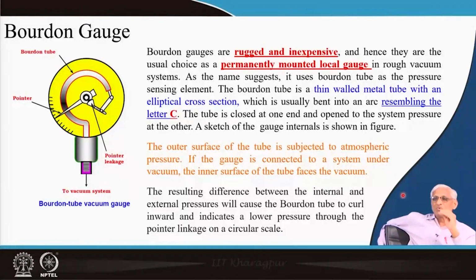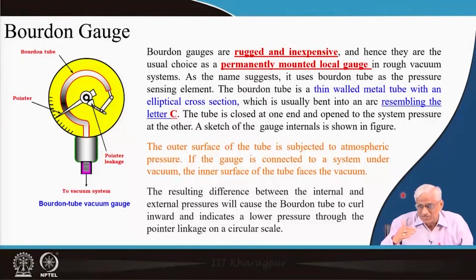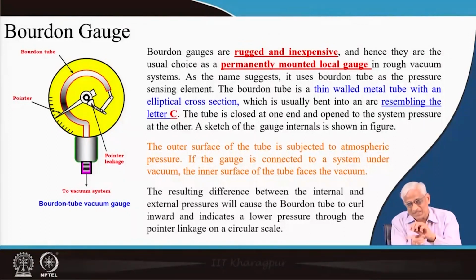But if you are using a purely vacuum gauge, its maximum point itself is 1000 millibar absolute. So this Bourdon gauge that I am showing you in the figure is a pure vacuum gauge, its upper limit is 1000 millibar. To be on the safe side, if there are pressure fluctuations, you can allow a little more on that side too, so that if pressure suddenly rises, the gauge will not get spoiled. But there are also gauges with both plus side and minus side combined.